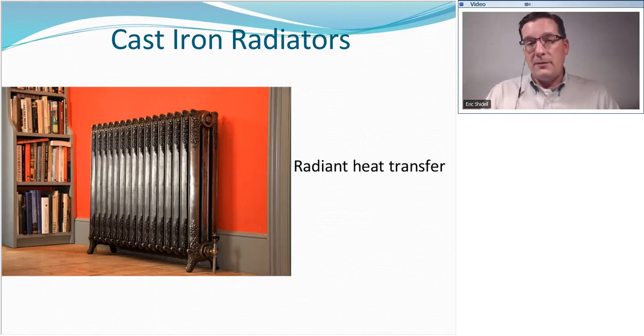You will see, in some cases, that people have taken an existing cast iron radiator and they build a box around it. They literally put a wooden box around it with an opening on the bottom and an opening on the top, and they are trying to turn the whole radiator into a convector. Why? Well, because radiators limit your ability to place furniture in the room. Because they heat the room with that line of sight heat shine, anything placed in front of the radiator is going to limit its ability to heat the space. Drapes, furniture, other stuff like that makes it really difficult to organize and decorate a room. So a lot of cast iron radiators have had shrouds built around them to turn them into convectors, which is a heat transfer using air.